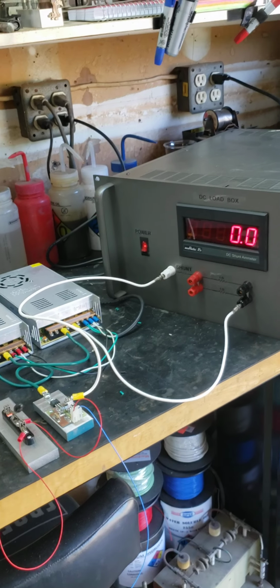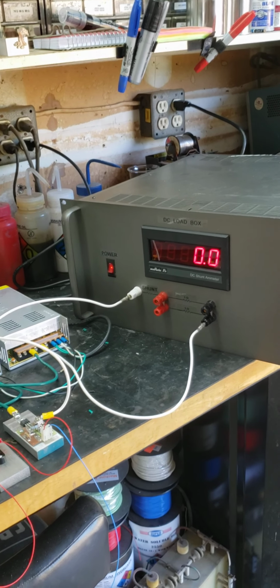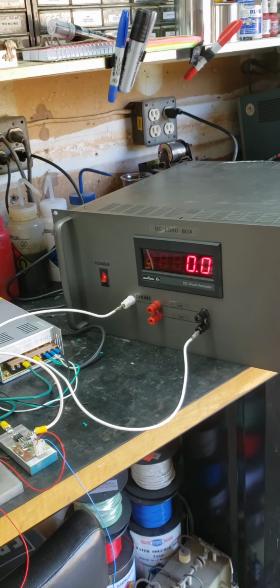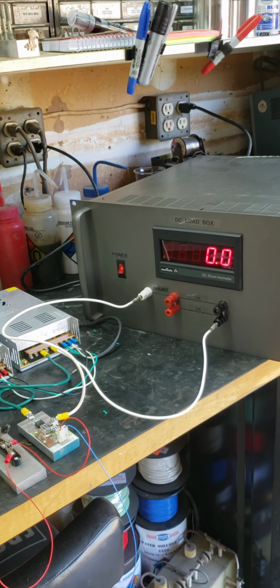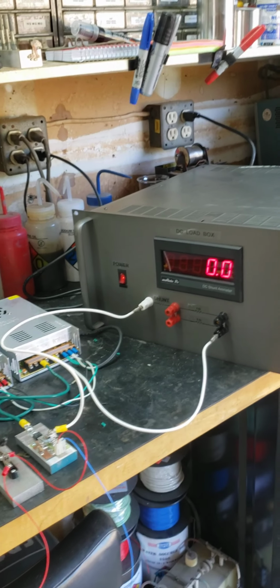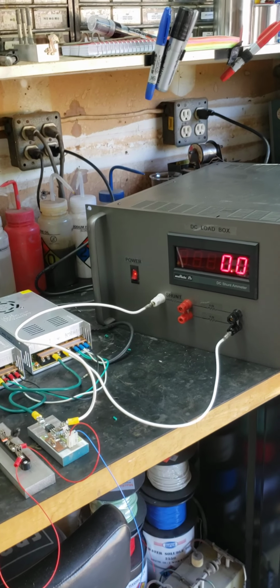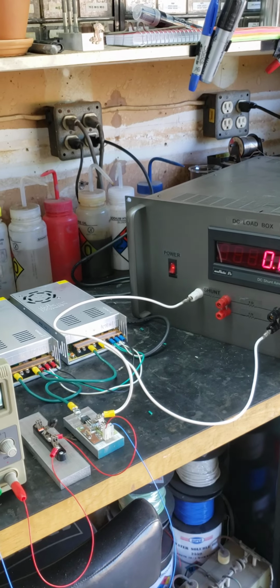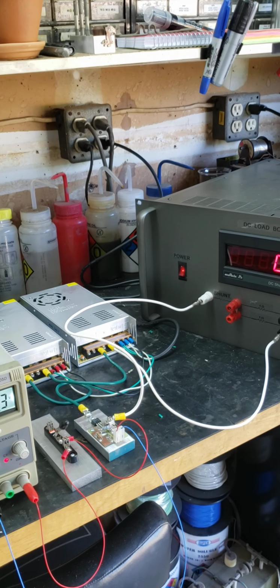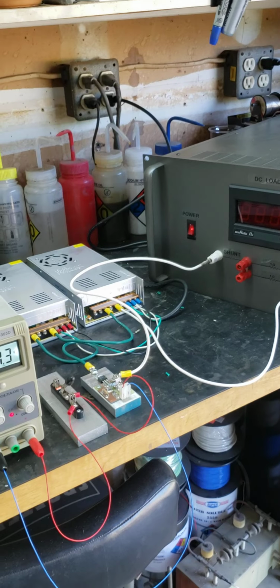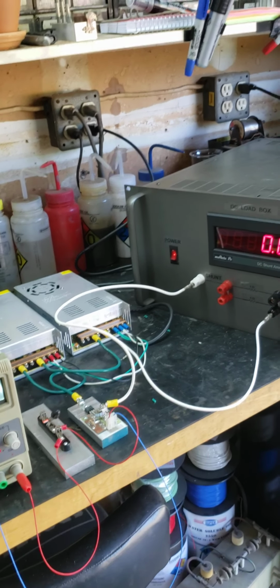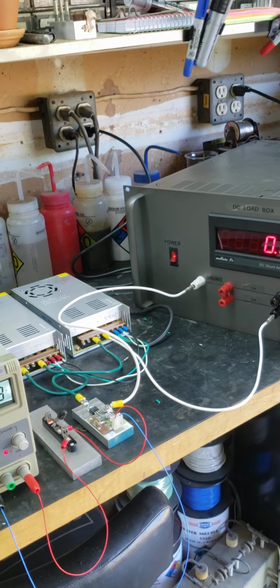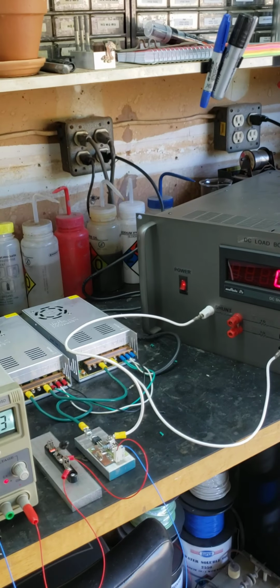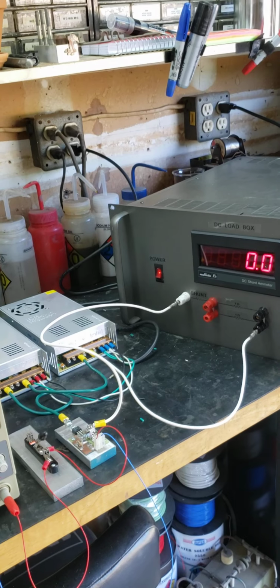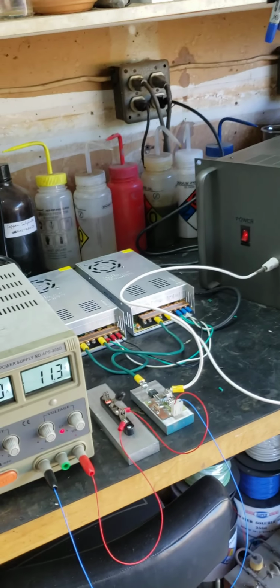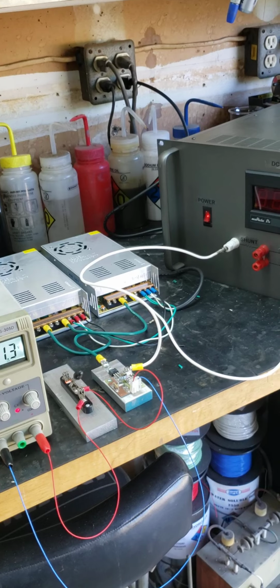But the ones coming from China are sized almost 100%, so you can't overdraw them at all. Their spec is their spec. There's no soft limit, it's a hard spec. So when they say 9.6 amps is as much as you're going to get out of that core, that's what you're going to get, because they're only magnetizing it with so much flux, and the core size can only handle so much flux. So, my mistake.